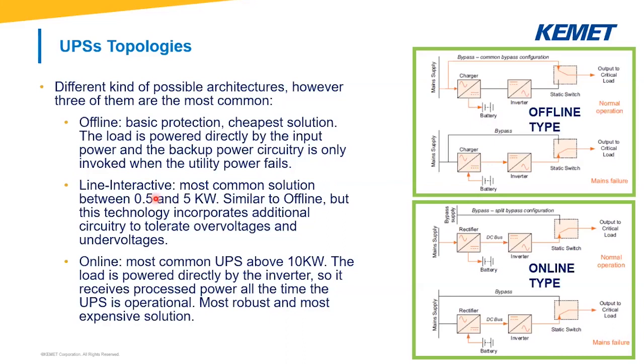The second type of architecture is the line-interactive. This is the most common solution between 0.5 and 5 kilowatt. It's really similar to the offline topology, but also incorporates additional circuitry to tolerate over-voltages and under-voltages, so the load is in some way protected from those input power conditions. Finally, we have the online topology, which is the most common UPS architecture above 10 kilowatt. The load is always powered directly by the inverter, so it receives processed power all the time the UPS is operational. This can be considered the most robust and most expensive solution.